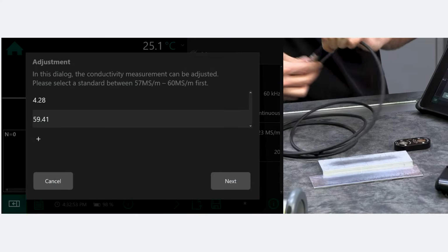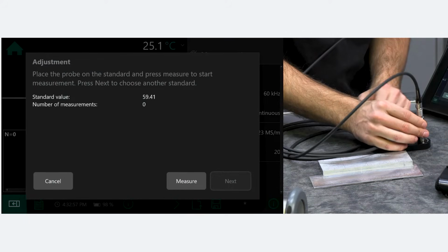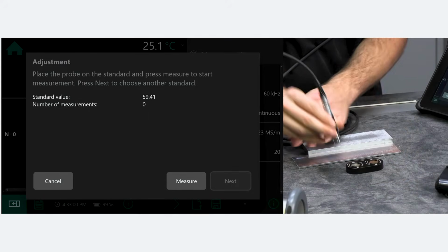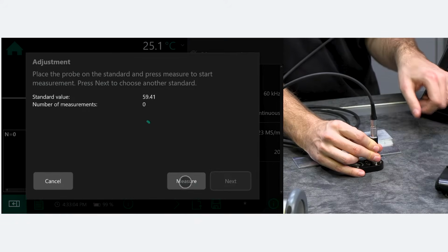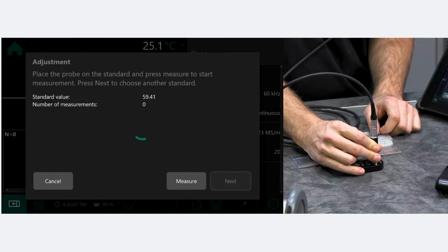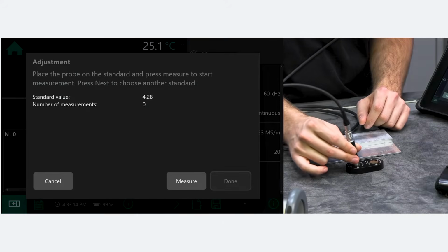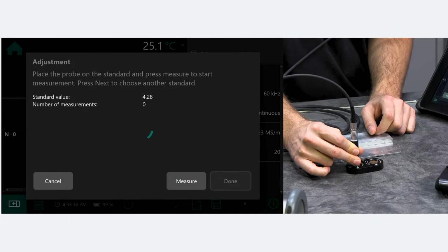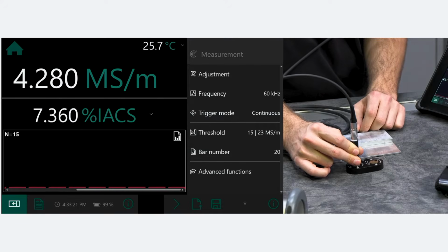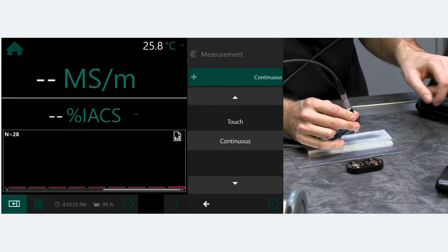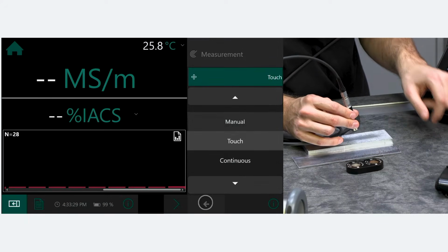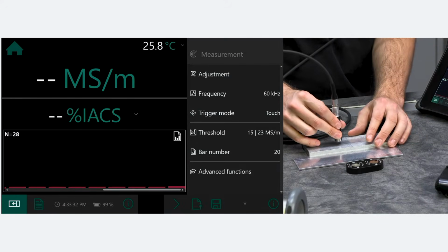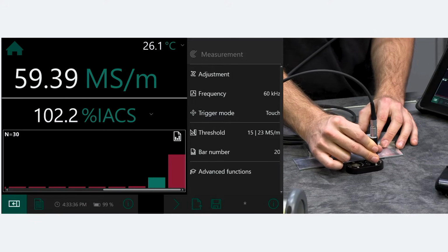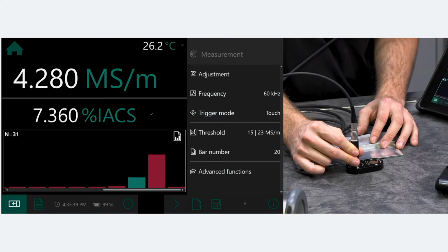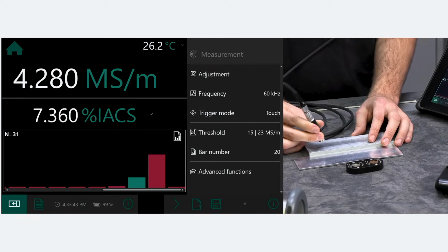So we go on our standard, click next, put the probe on the copper material, click measure. Okay, measurement done. Next standard, put it on the other one, measure, and done. Okay, someone set up the continuous mode before, so we will start with touch mode. On touch mode, it automatically reduces the sampling rate because then it's better to use. And now we can control our standards, okay, 59.39 and 4.28, so exactly the values we set up before.